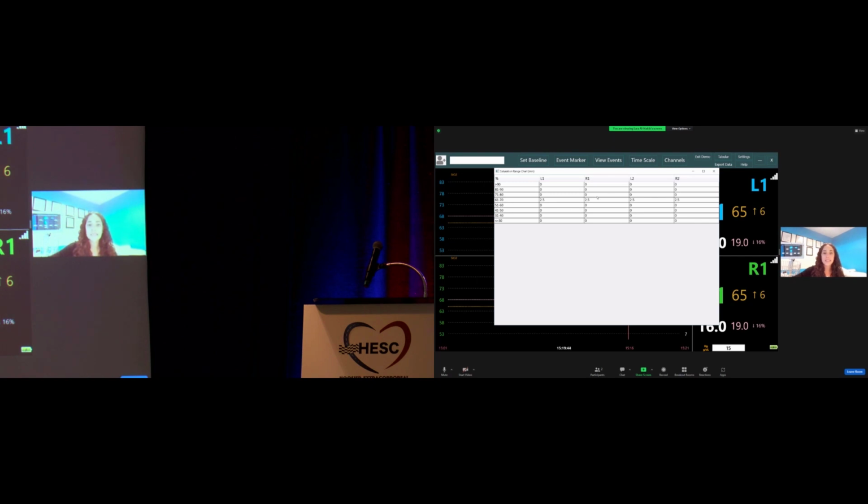And so as you can see here, the patient or the mock patient, since we're in demo mode, has spent about 2.5 minutes in the range of 61 to 70% saturated. If the patient had gone through a desaturation event, their time would be calculated anywhere over here, which would give us an indication of how severe the desaturation event was or any sort of measures that we would need to take afterwards.